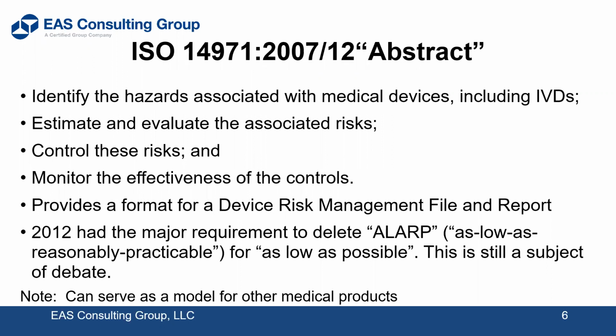Now, the old 2007, 2012 abstract mentioned these kinds of requirements as well. And they talk about the ALARP, as low as reasonably practical, or that was changed to as low as possible in 2012. And that was a source of much confusion in the industry. Hence, one of the key reasons why 14971 was revised again in 2019. But it also changed the report to review the summation of this activity, and further increased the going beyond the device itself to your system, having a risk management system in place that's defined, as well as the risk management analysis of individual devices. And like I mentioned, I use the model that we'll be talking about here also for pharmaceuticals or dietary supplements under ICH Q9. That doesn't mean you have to, but it works pretty much the same way.